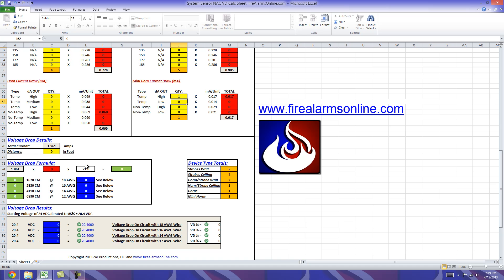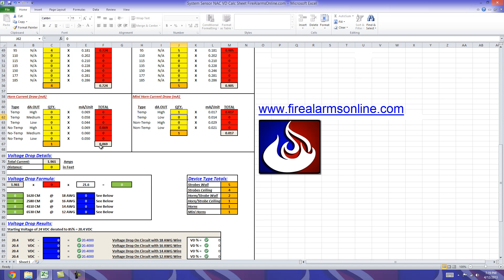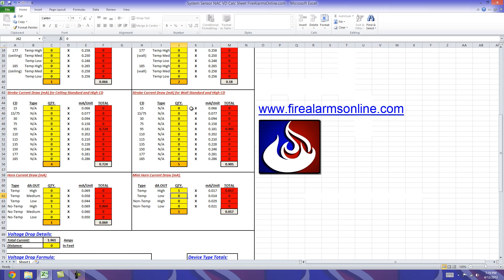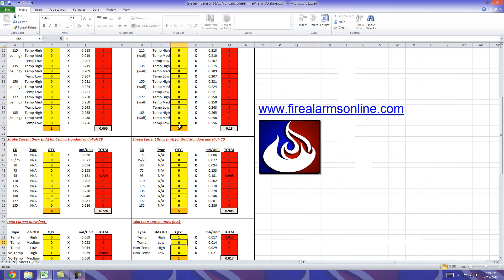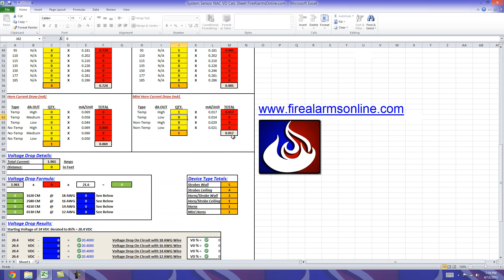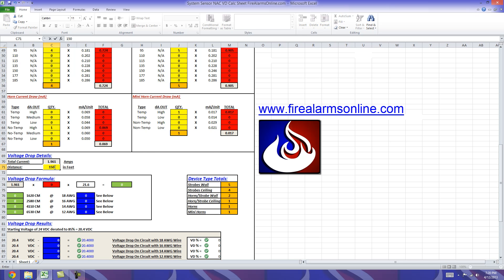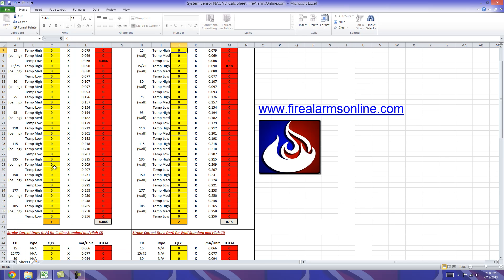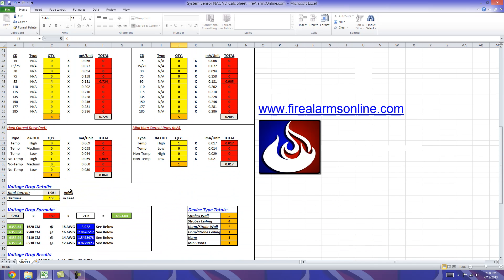Now all the gray cells at the bottom of the red columns are keeping track of the total current. And to keep it simple we color coded it down here to your voltage drop details and your total current is 1.961 amps. And once again like we discussed, the yellow cells you can edit. So here is where we're going to put the distance of our circuit and just for the sake of the demonstration we'll go ahead and put 150 feet and put that in there.